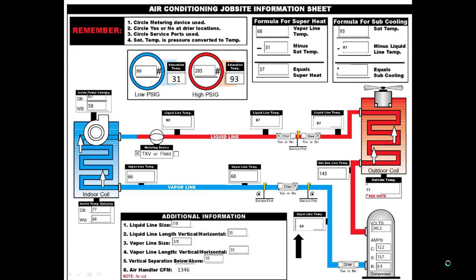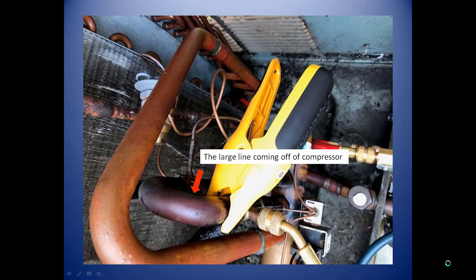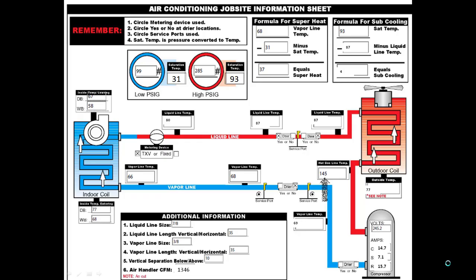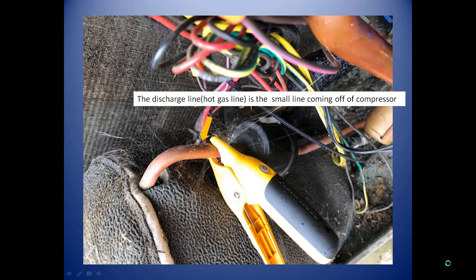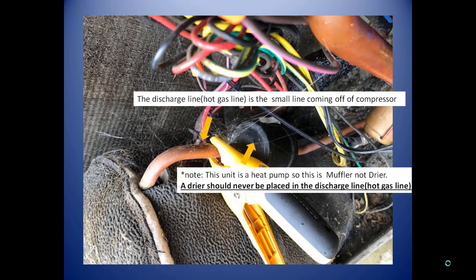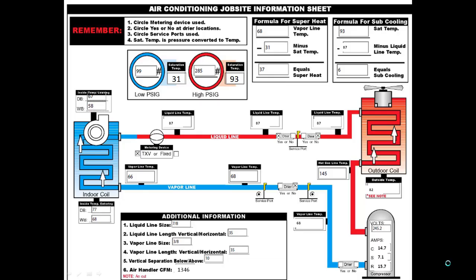Also, we need to make sure we get into the unit and get that vapor line temperature about 6 inches from the compressor. As you can see here, we're taking this reading right off the reversing valve. This is a heat pump, so we're going between the reversing valve and the compressor. Hot gas reading, we'll take that also on the inside of the unit, about 4 to 6 inches from the compressor. What you're seeing here in the picture is a muffler, not a dryer.